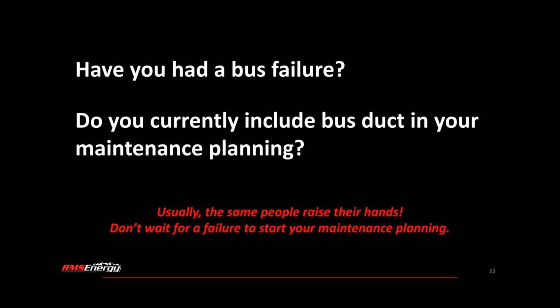Sure. Well, generally, an overheating issue in the enclosure and the PD in the insulation are probably not coming from the same issue, but I wouldn't rule it out necessarily. So I think what we probably need to do is look at your specific situation and what's attached to your bus duct, the type of design and materials used, and the manufacturer, to be able to investigate a little bit deeper. Sure, and we'll probably just reach out to you guys then. Thank you.